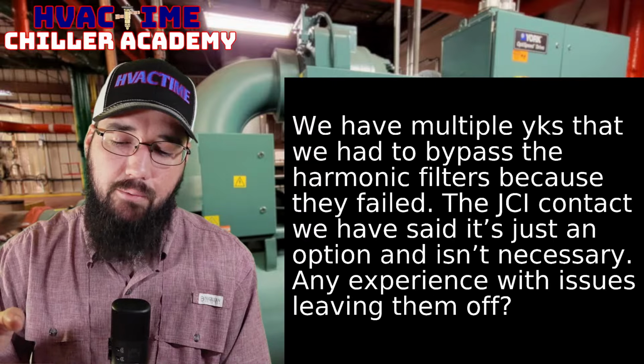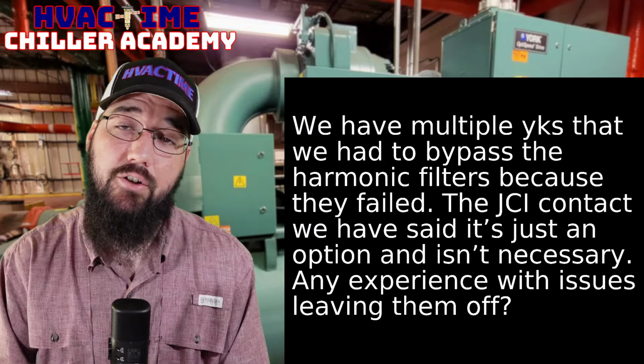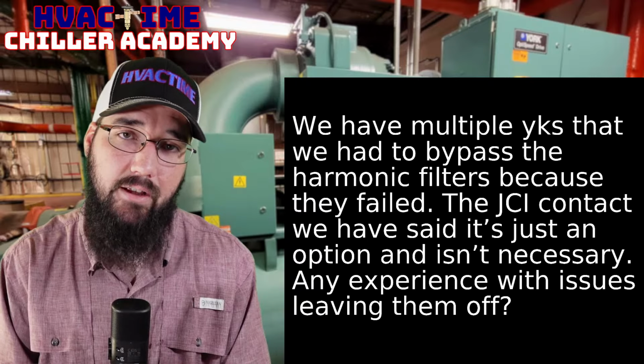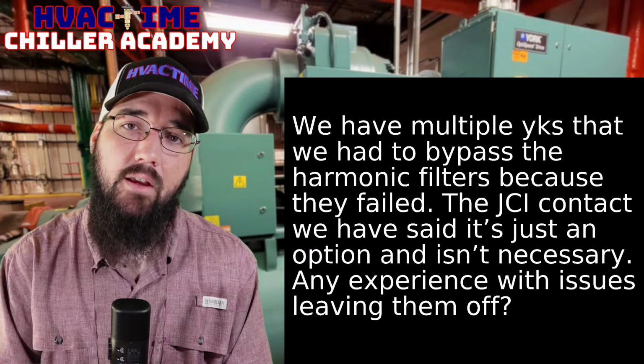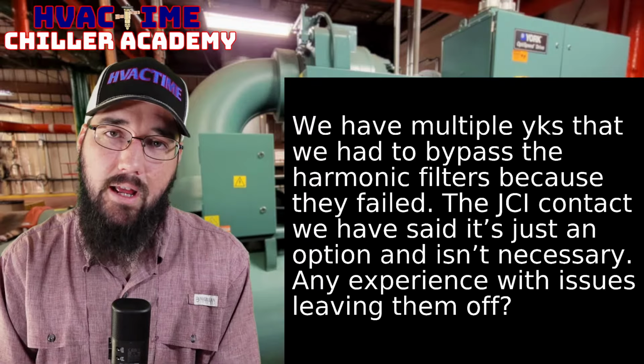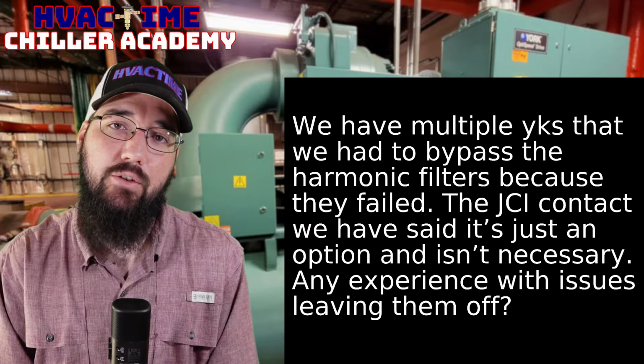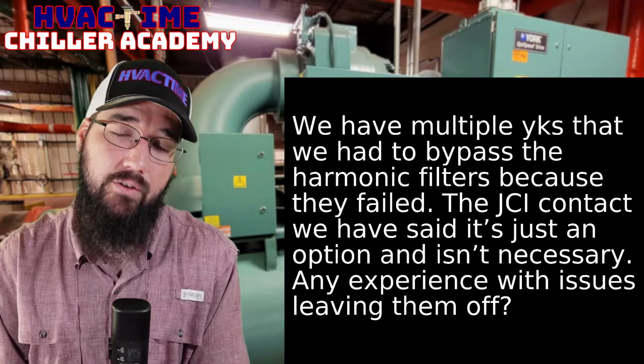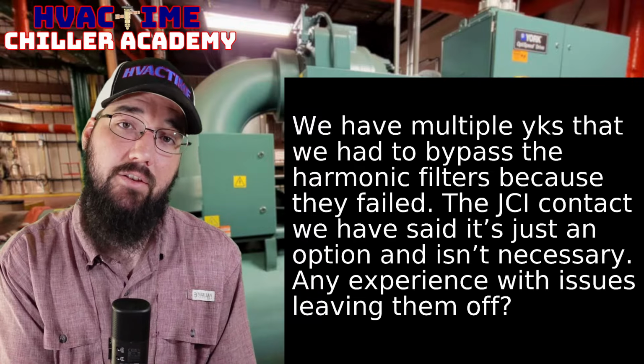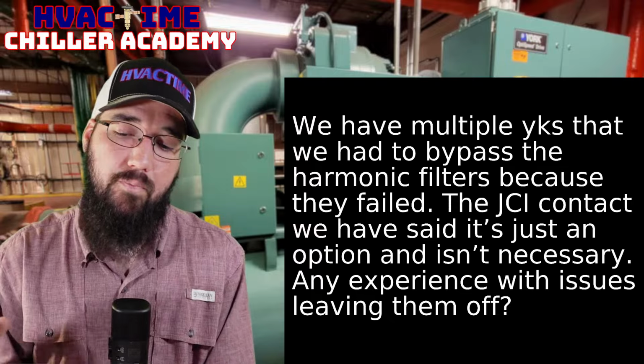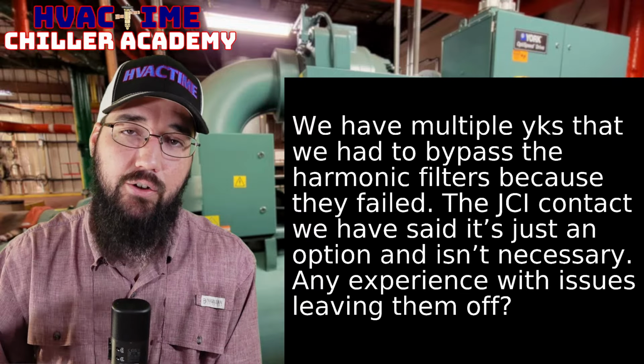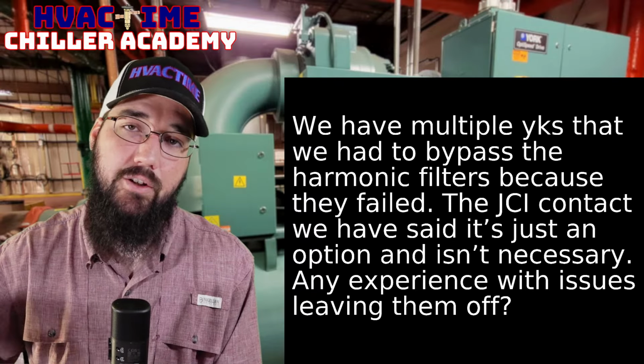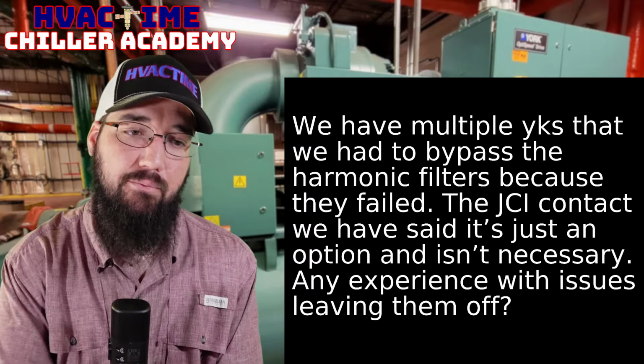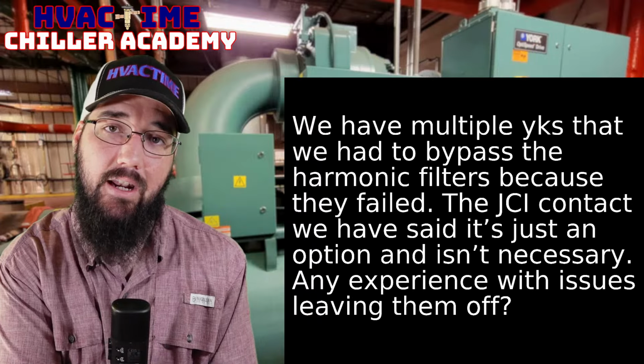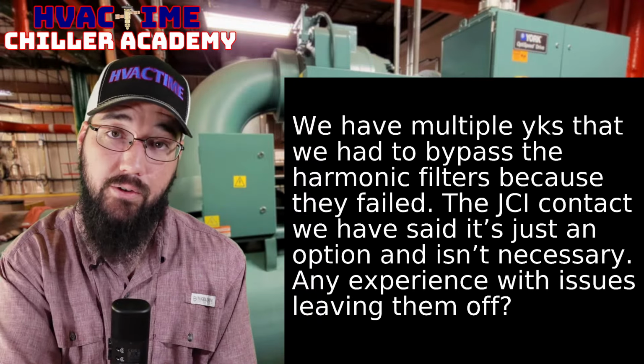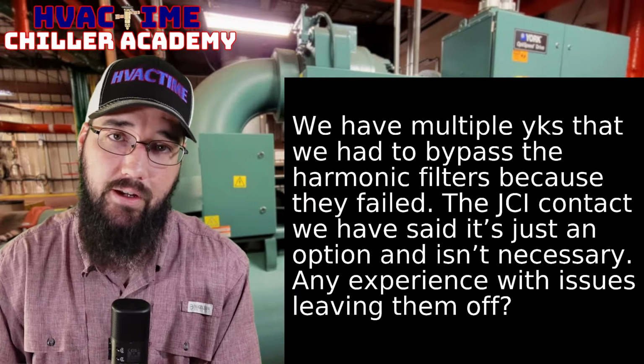So that rectification process ends up actually creating a lot of backfeed static that can get into the grid. Now, these drives have reactors in them to try to not only filter the static noise coming into the drive, but also clean up the static the drive is creating. So if that reactor isn't there, there are situations where that drive can cause a significant amount of backfeed static into the main grid for the building, and that can cause all kinds of other things to start freaking out.